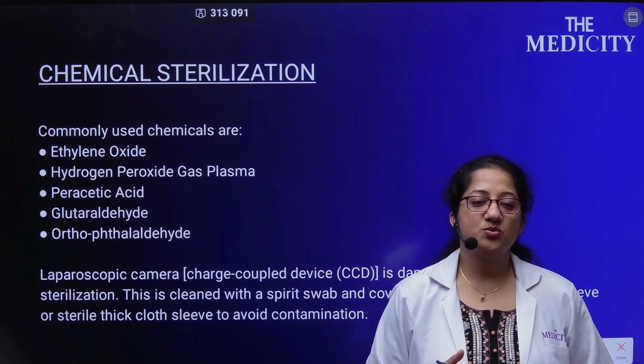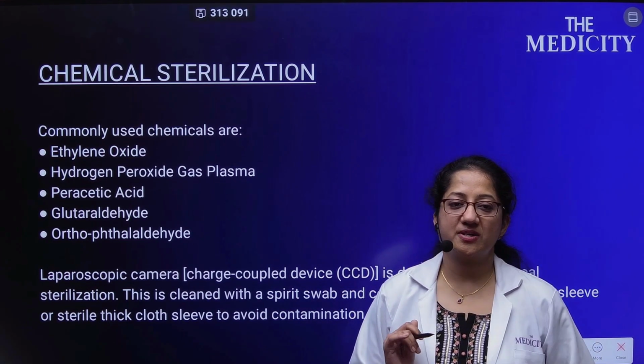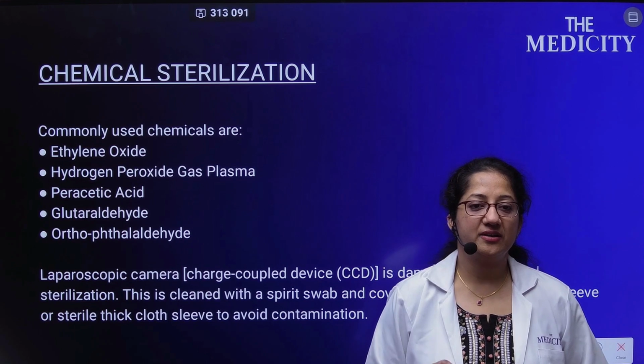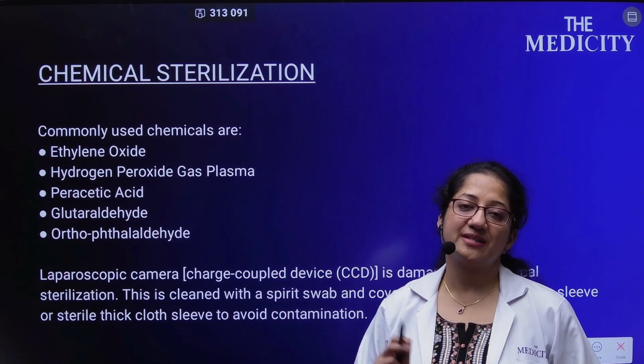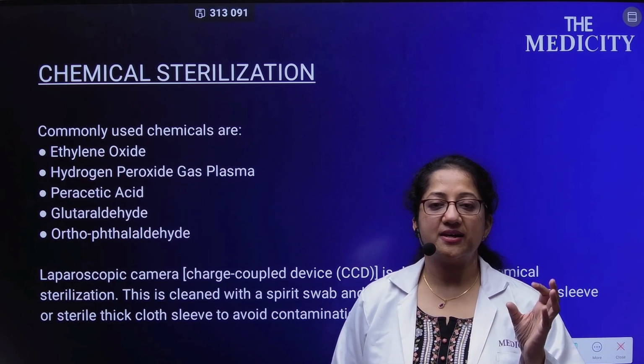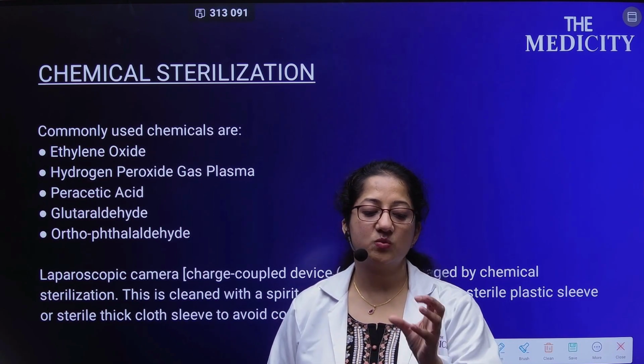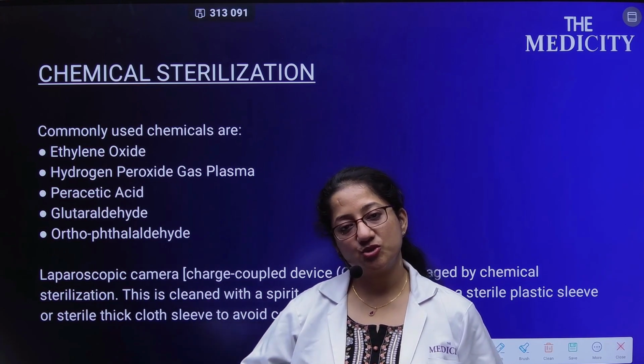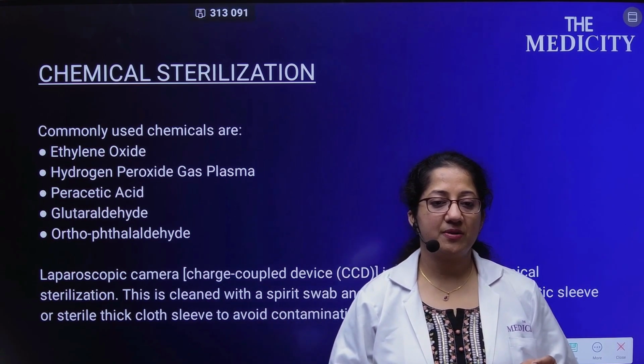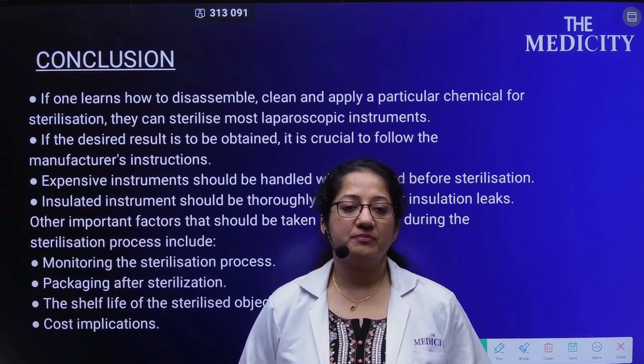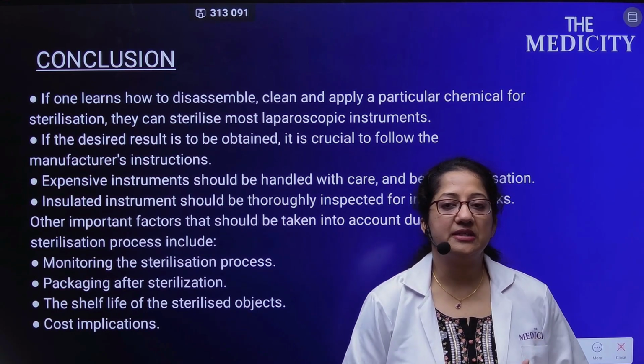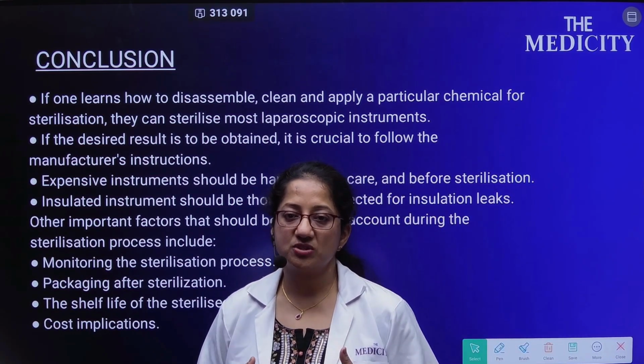Chemical sterilization uses ethylene oxide, hydrogen peroxide, gas plasma, peracetic acid, glutaraldehyde, and orthophthalaldehyde. The laparoscopic camera charge-coupled device is damaged by chemical sterilization. The camera is always given after cleaning with the sanitizer through gauze, and then it is held with sterile gauze and given in a sterile plastic bag through which it is attached to the laparoscope. It is covered with a sterile plastic sleeve or a plastic cloth, and that is to avoid contamination. So basically, if we learn how to disassemble, clean and apply the particular chemical for sterilization, it can be done more effectively.